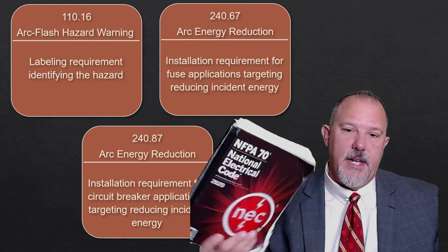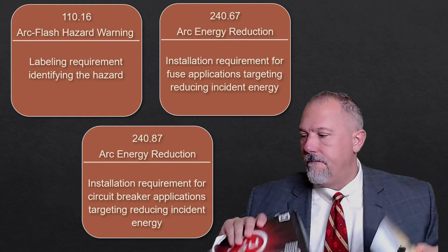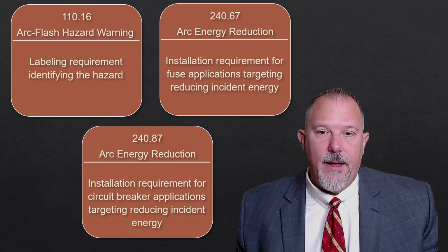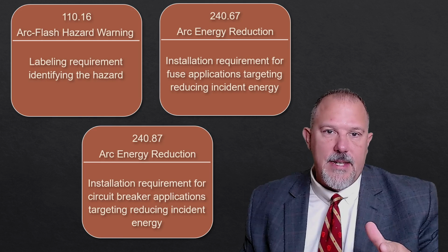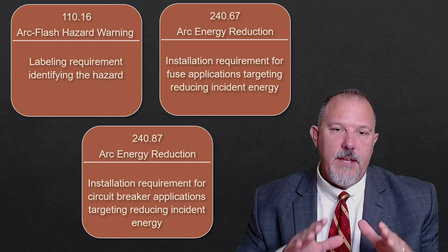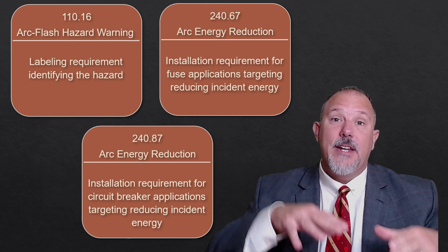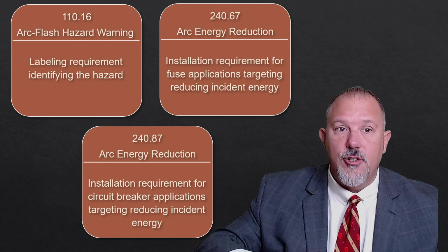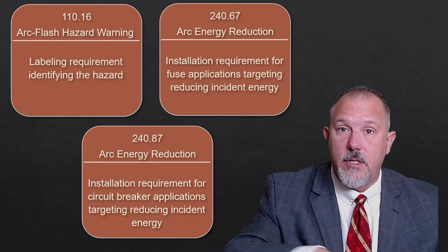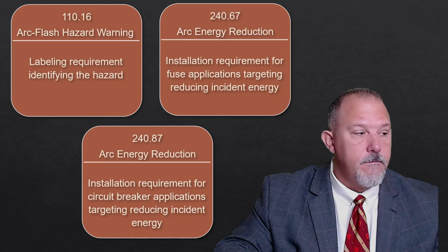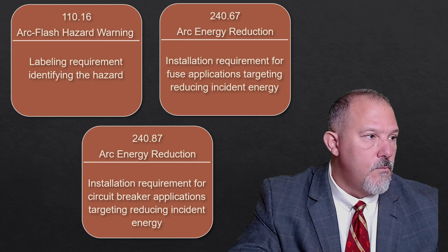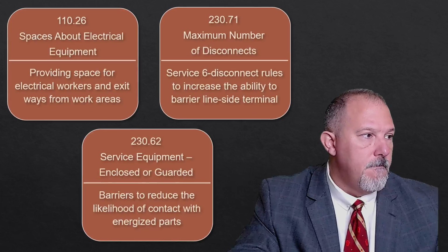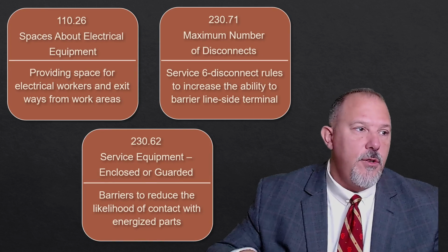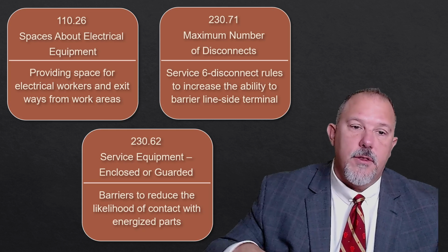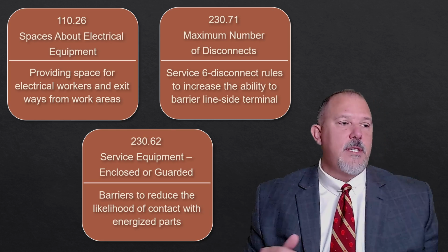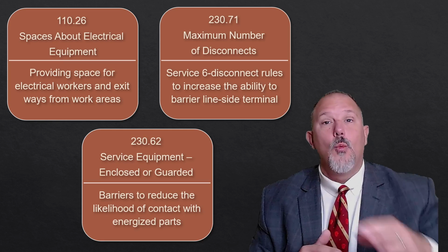Anyway, two important documents you should always have, 70 and 70E. So I've got them both accessed pretty close. 110.16, 240.67, and 240.87, three very important sections in the National Electrical Code that directly relate to incident energy and are of recent introduction. 110.26, 230.71, and 230.62. So these, I would say, are related requirements. Why? We're going to get into that.